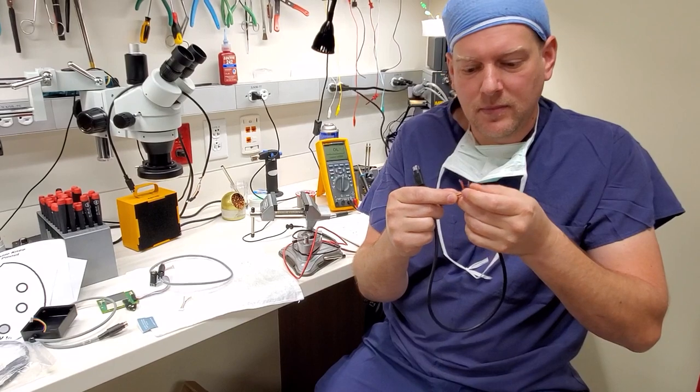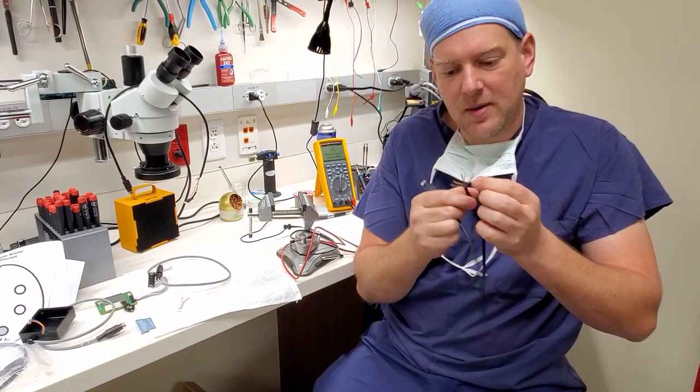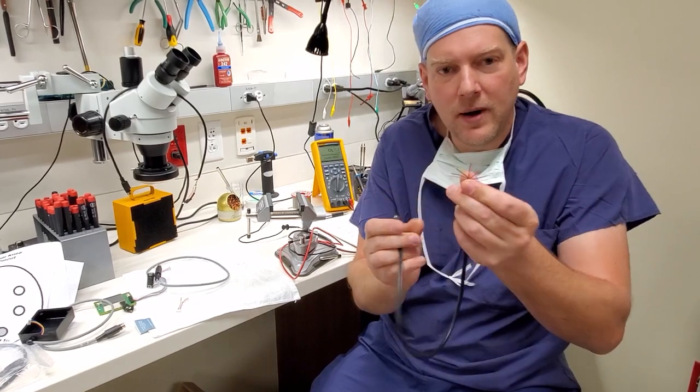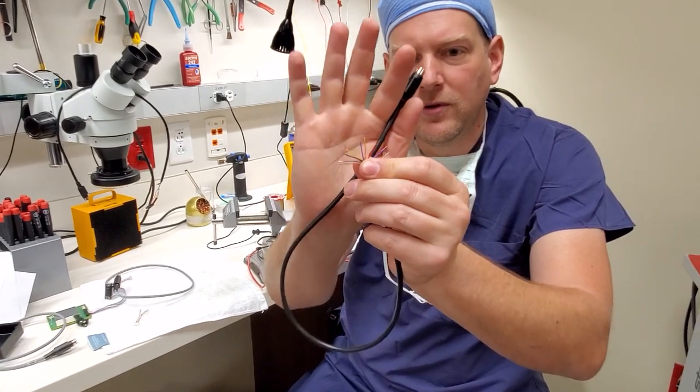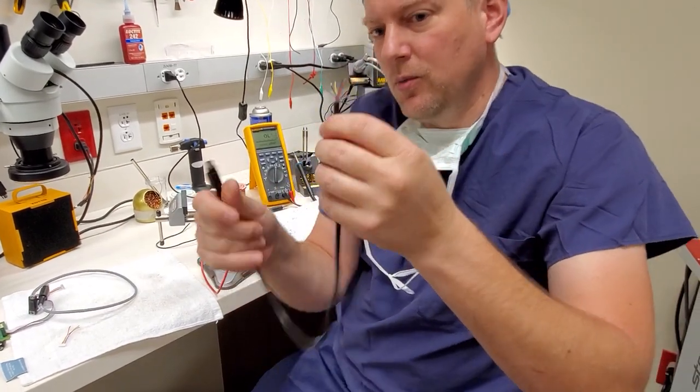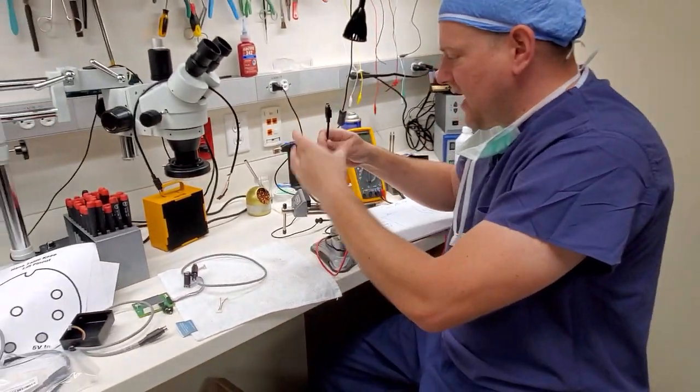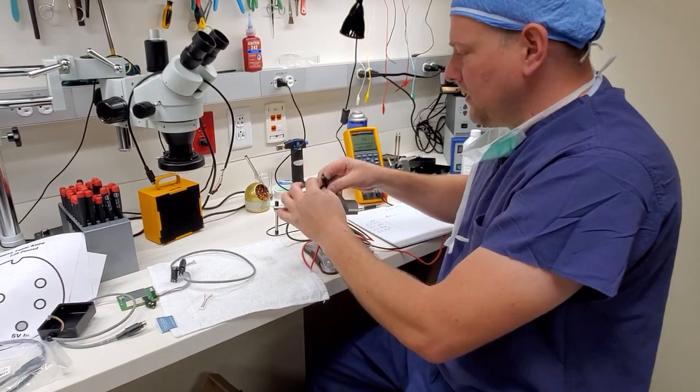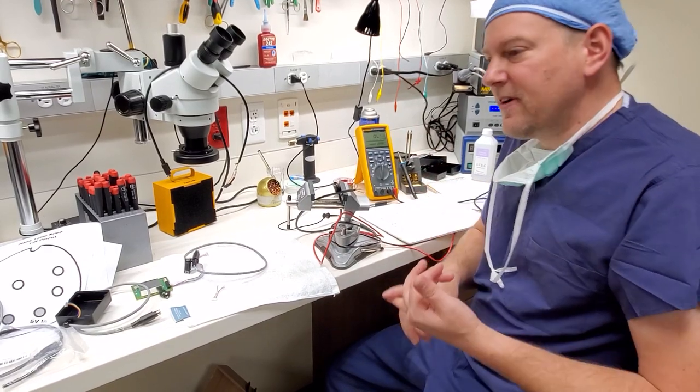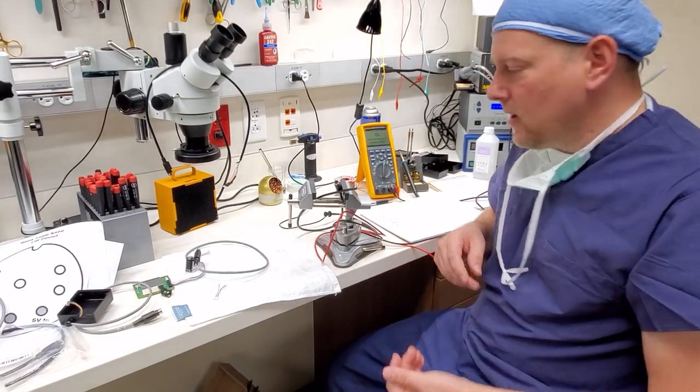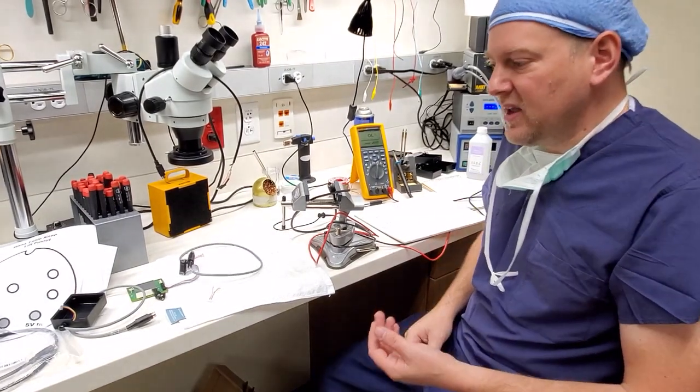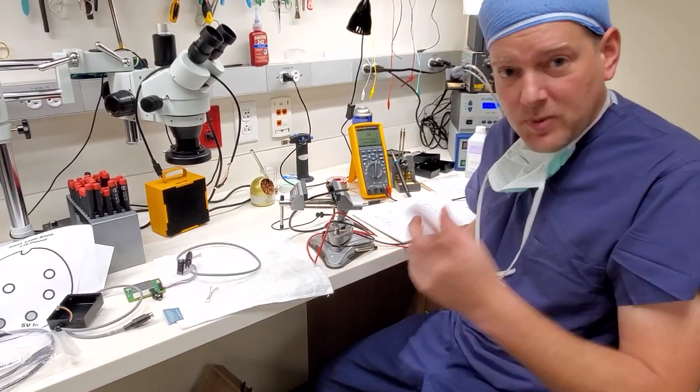You strip it back so that all the wires are separate and the little bit of ends are barely showing. I don't know if you can see that or not. So I have all the pins separated and we are going to go ahead and set this guy in the device. Now you can't do color code to color code, cable to cable because every manufacturer is going to have a different color pin out and you're going to have a whole bunch of variety. So always check your pin out before you start soldering stuff up, especially on medical equipment.